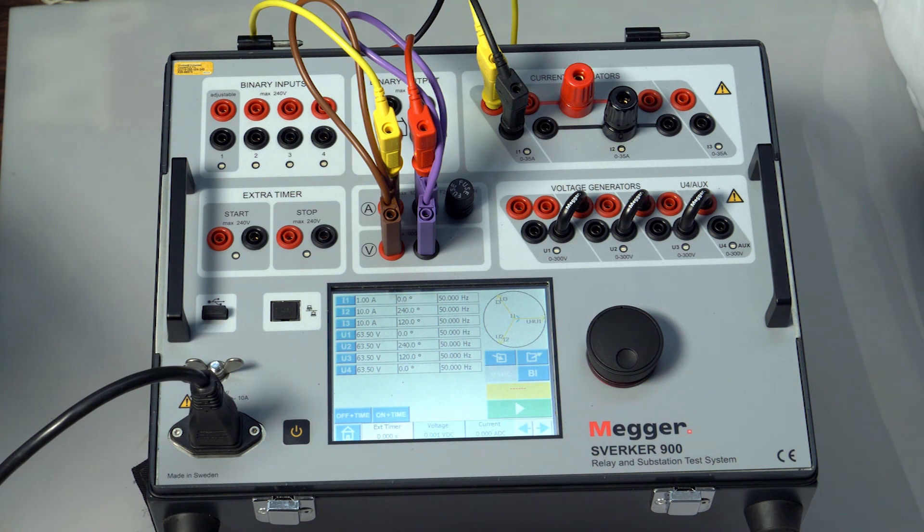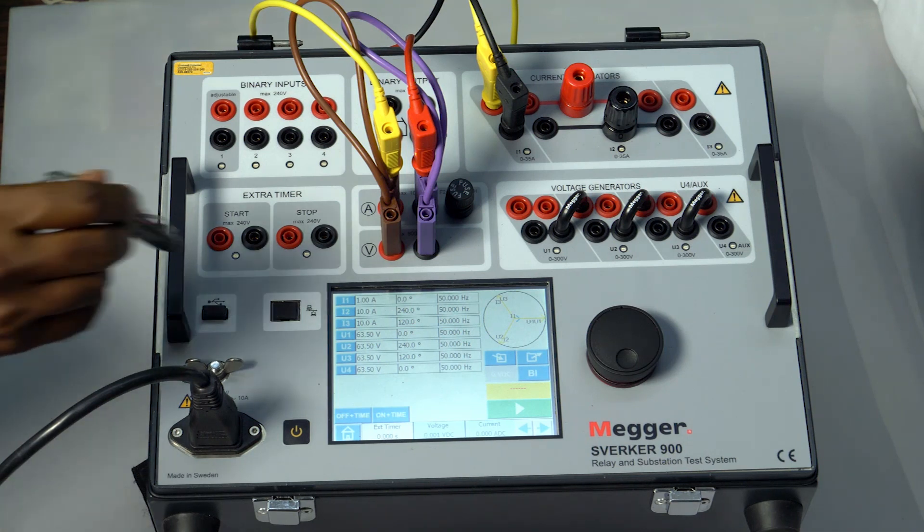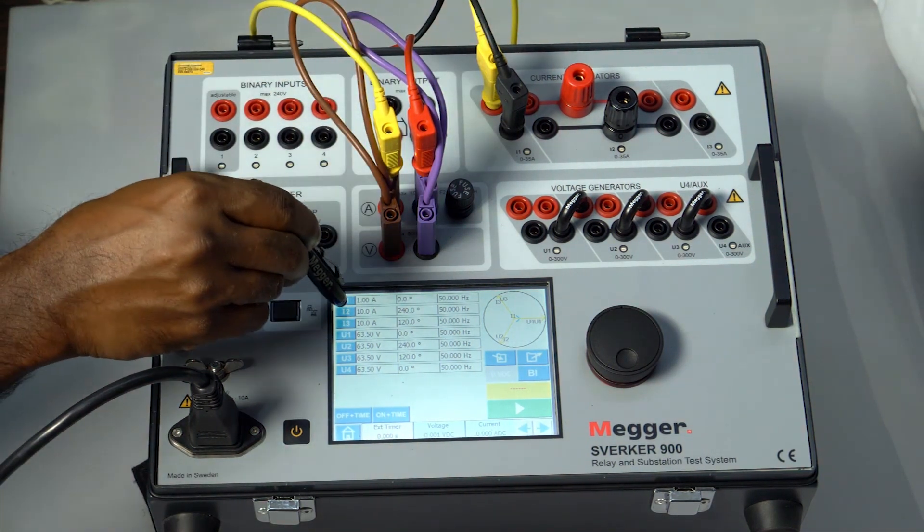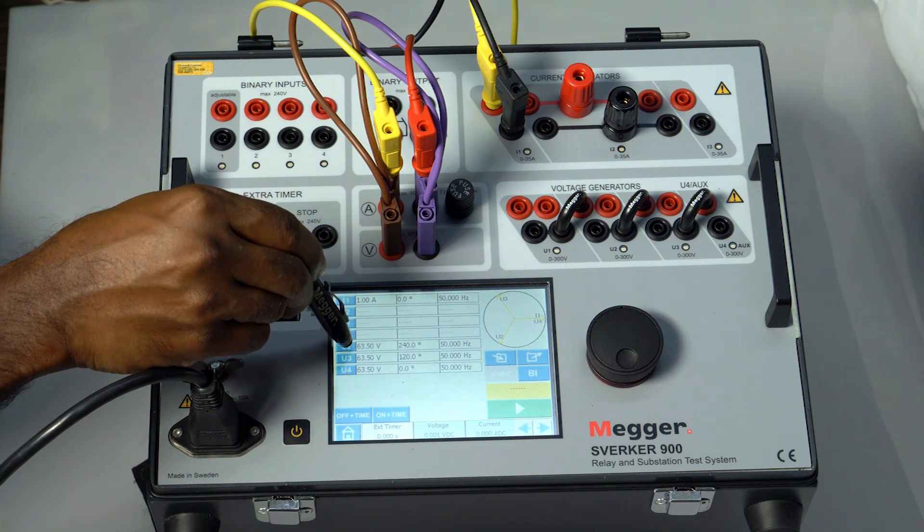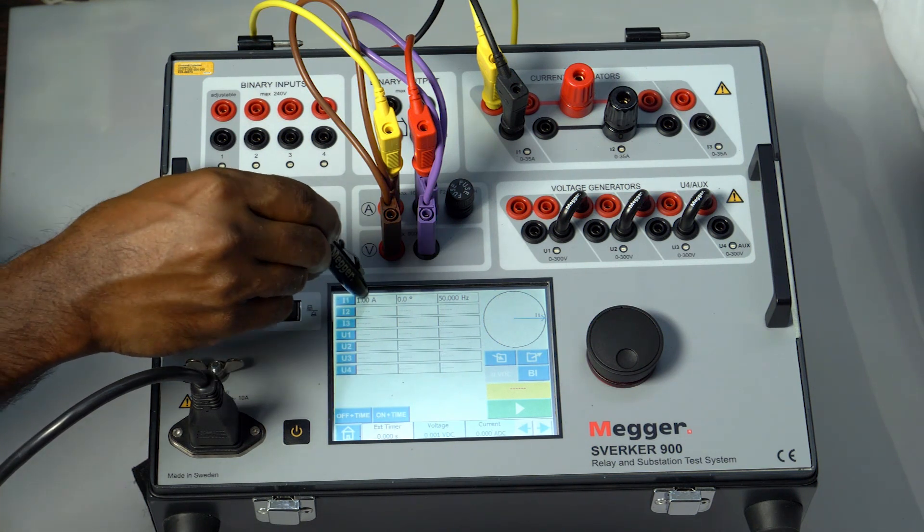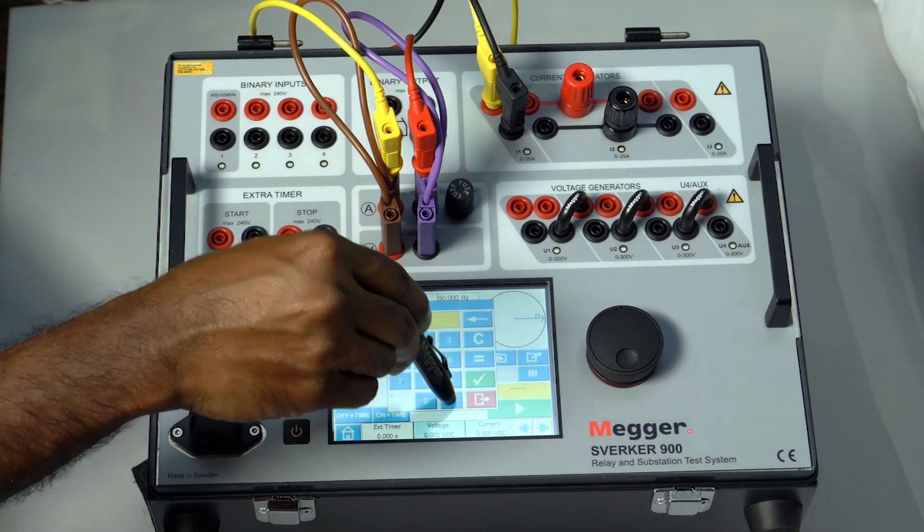Inject 10% of the rated CT secondary in DC. 0.1 amps is 10% for a 1 amp CT secondary. We have connected only to the R phase of the test kit, so let me turn off all the other sources and inject 0.1 amps DC.